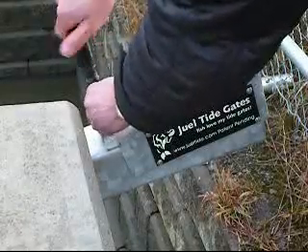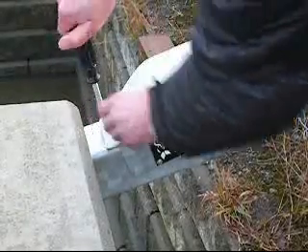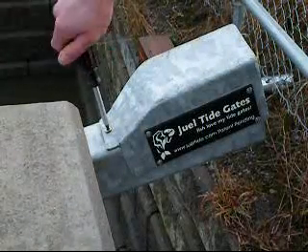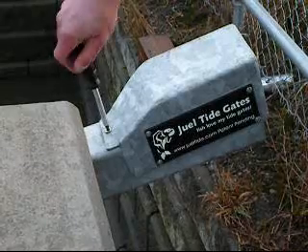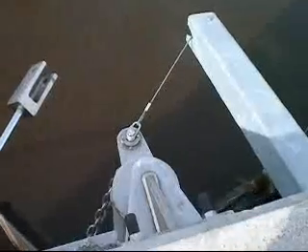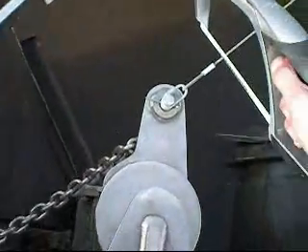The only exposed and vulnerable component is the light gauge wire rope. With some work, a determined miscreant could cut it using a hacksaw or cable cutters. Stainless steel wire rope is readily available and the replacement cost would be less than $20. The time required to replace the severed wire rope is less than an hour. While awaiting repairs, the tide gate would be a free swinging flap gate and it would not result in flooding.